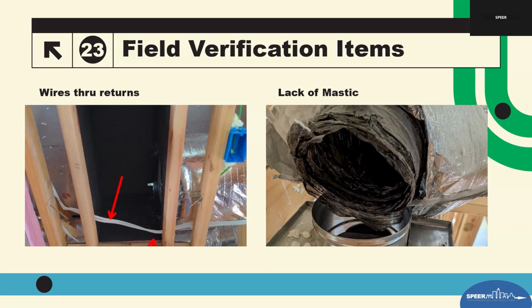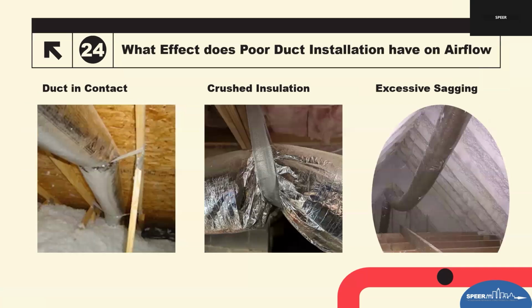And then on the right, we see lack of mastic. Clearly, if we roll the insulation back, which some cities in Texas require insulation to be left off to see the collars and the connections and the fittings to make sure that it has mastic. But in this case, it has mastic, it's just not in the right place. So we need to have mastic on the collars, on the boots, on the fittings, on the Ys, on the Ts, and then put the inner liner on it, not put mastic on the outside of the liner to look like and appear that it has been mastic. And that still is seen a lot in the field in Texas.